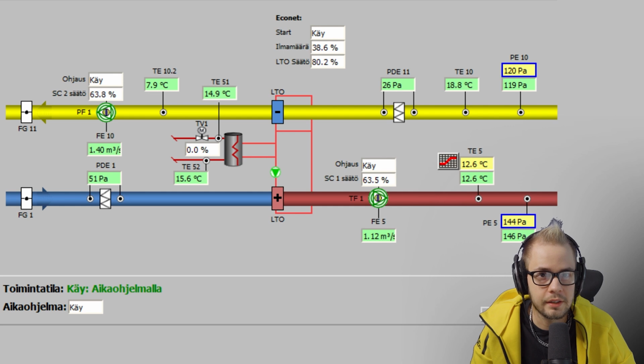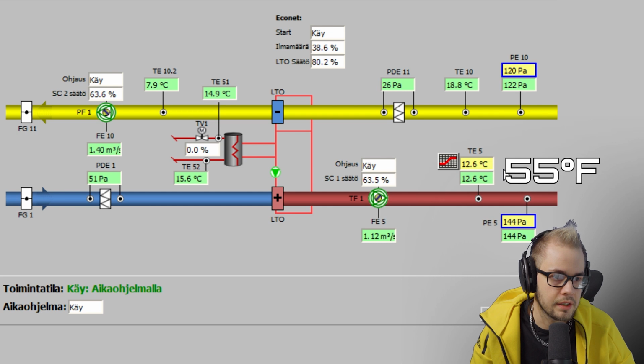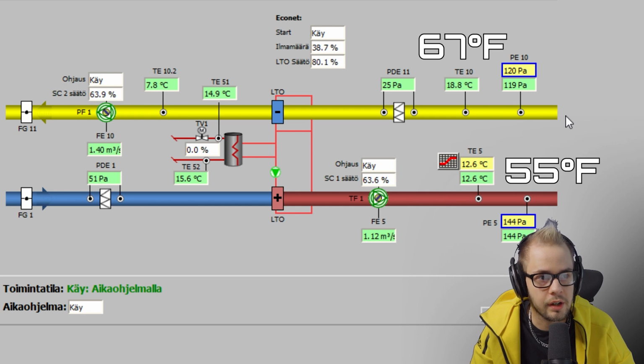Here is the heat recovery ventilation schematic. On the lower pipe here you can see there's the input shutter, then there's the filter, then there's the heat exchanger loop, and the motor, and there are the pressure and temperature sensors. Currently the machine is requesting 12.6 degrees air and it's getting what it wants. The yellow pipe is the exhaust and currently it's getting 18.8 degrees Celsius out from the apartments.